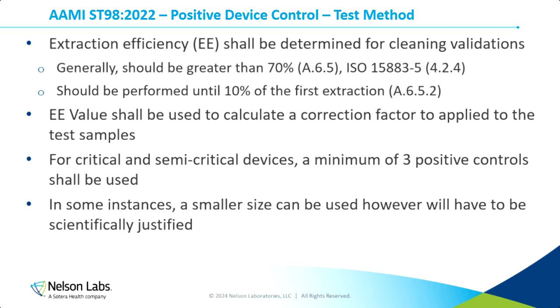The extraction efficiency value is then used to calculate the correction factor that is applied to the test articles. For critical and semi-critical devices, a minimum of 3 positive controls shall be used. So that ends up totaling 12 extractions, 4 extractions per positive control. In some instances, it may be possible to justify using a smaller size, but you definitely need to have a good documented scientific justification behind that.